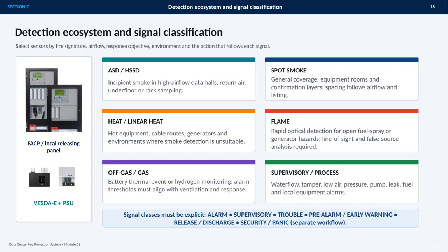This section focuses on the detection ecosystem and how each signal should be classified. The key principle is to select sensors based on the fire signature, airflow, response objective, environment, and the action that follows the signal. For high airflow data halls, return air paths, underfloor spaces, or rack sampling, ASD or HSSD systems, such as VESDA-E, are designed to identify incipient smoke early. Spot smoke detectors provide general coverage and confirmation, with spacing adjusted for airflow and listing.